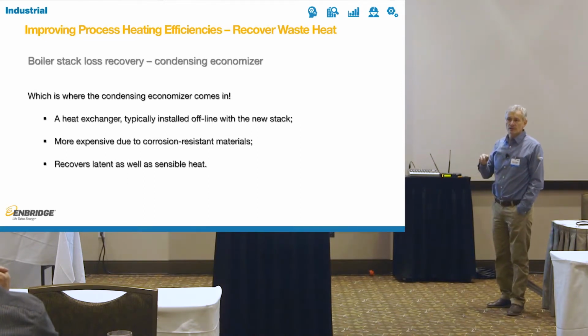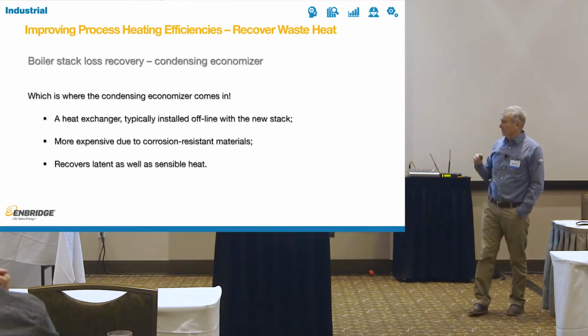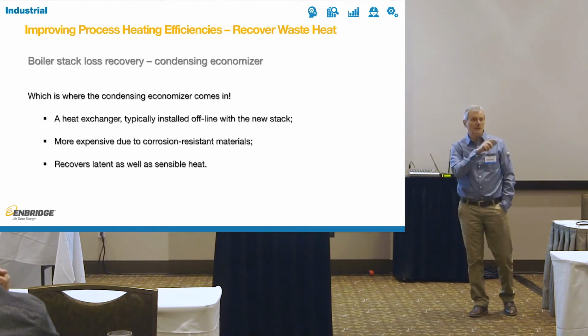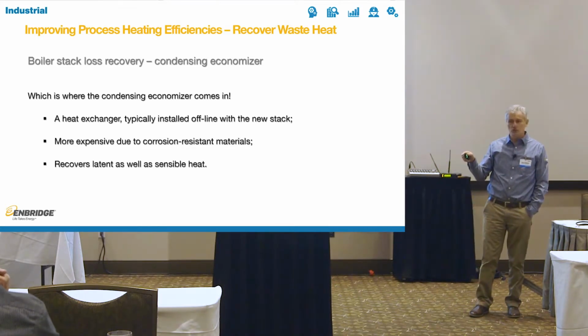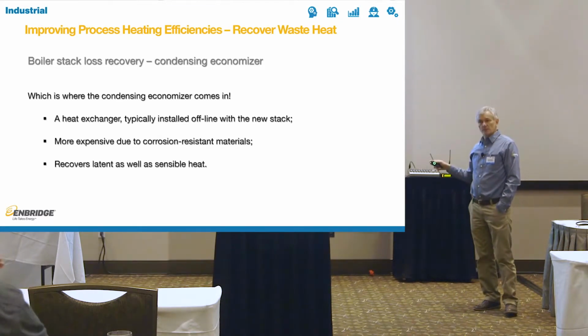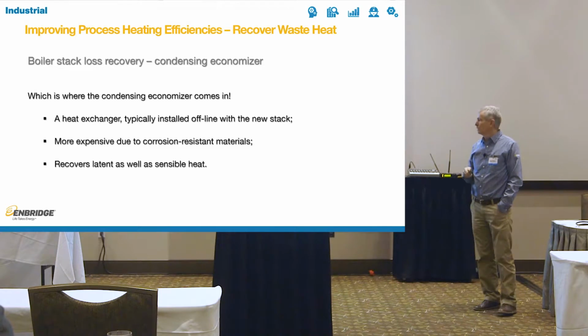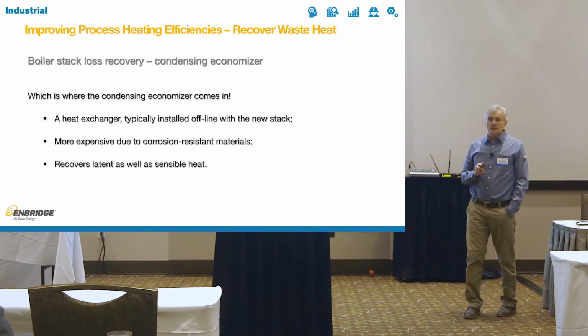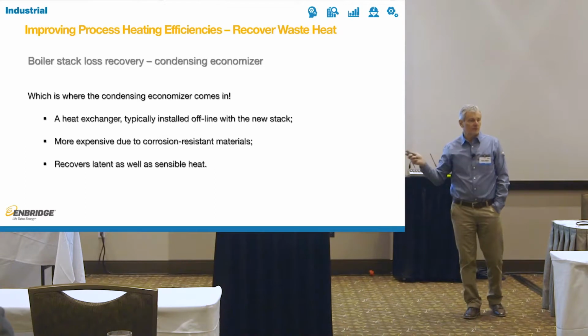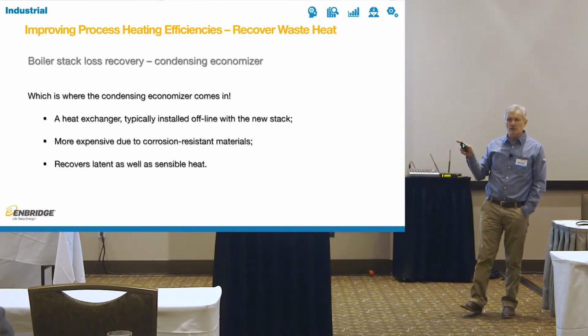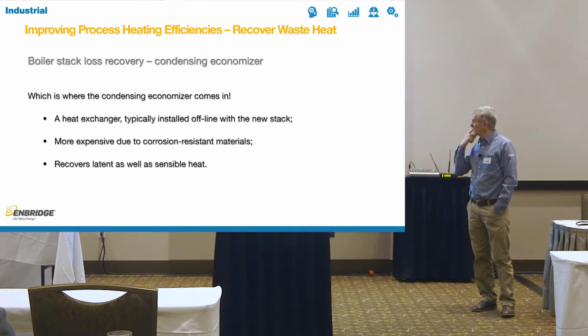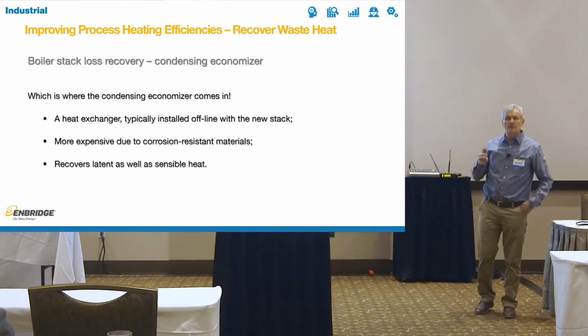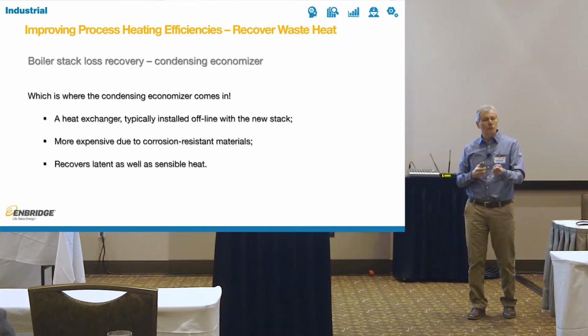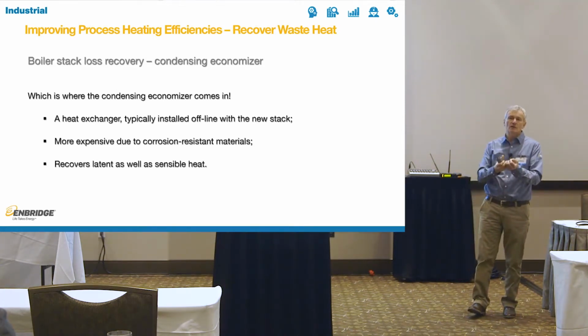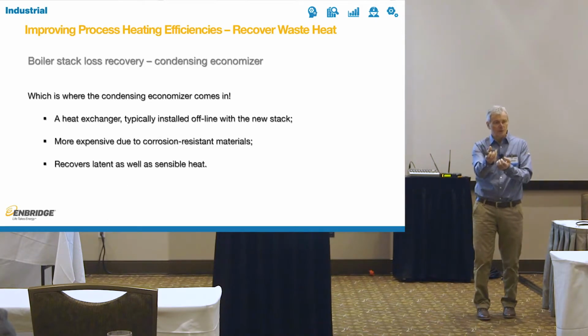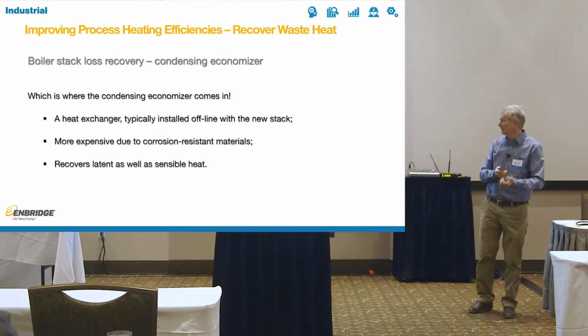That's why you have condensing economizers. You will often see them as a heat exchanger installed either in the stack or on the side as a separate installation. It's more expensive because it's corrosion resistant, but it recovers latent heat as well as sensible heat. Again, we have different workshops where we discuss the benefits of latent versus sensible heat, but latent heat just means that we can actually condense some of the water out of the flue gas. By condensing the water, you're getting back the energy that was needed to vaporize the water in the first place. And that's actually where the savings are.